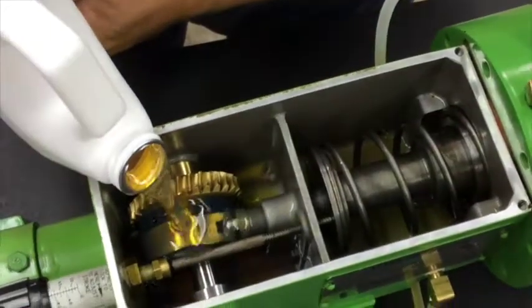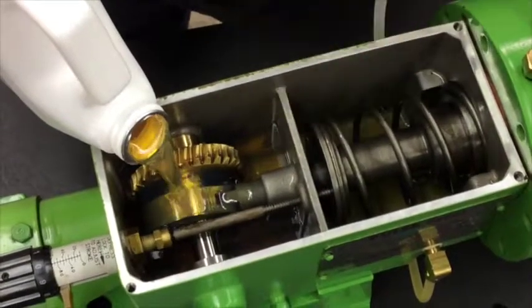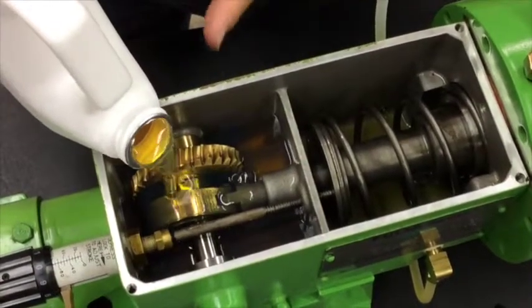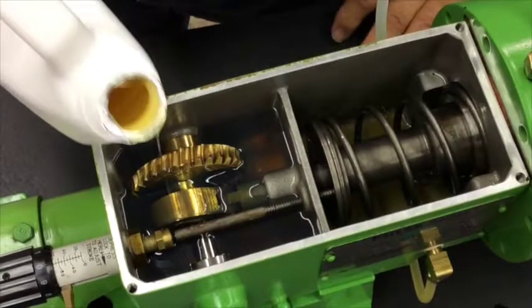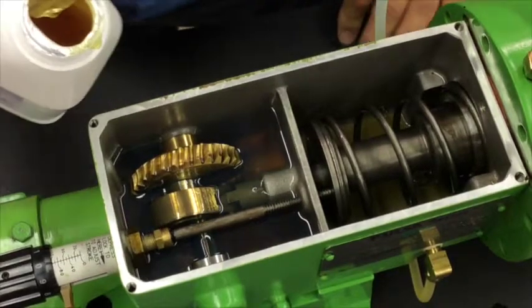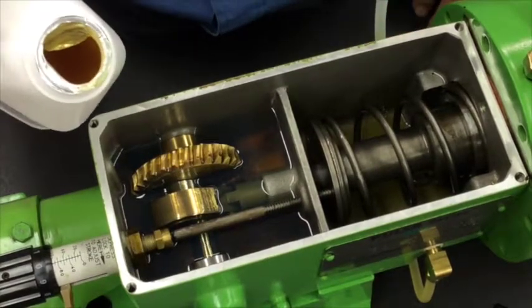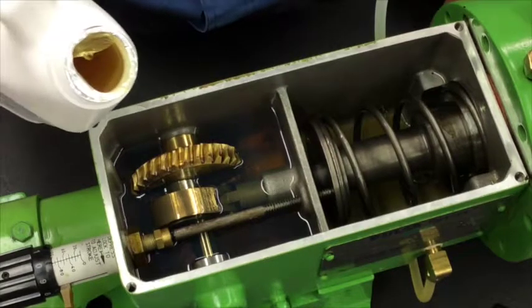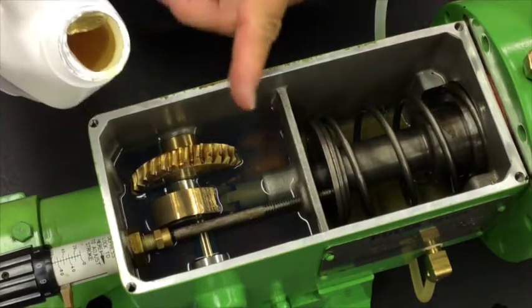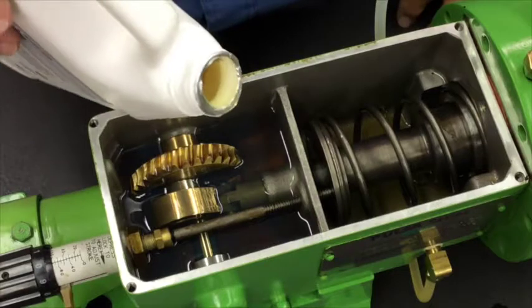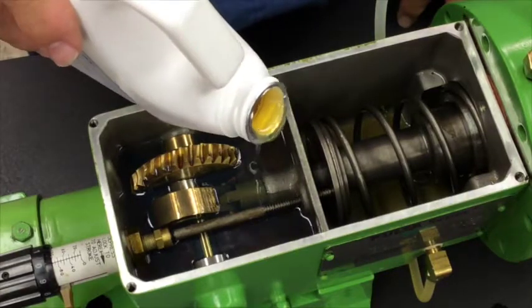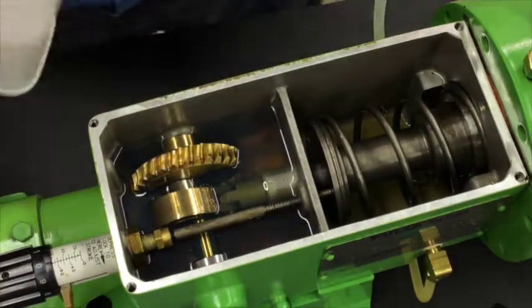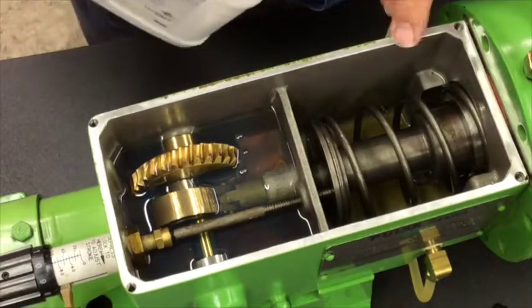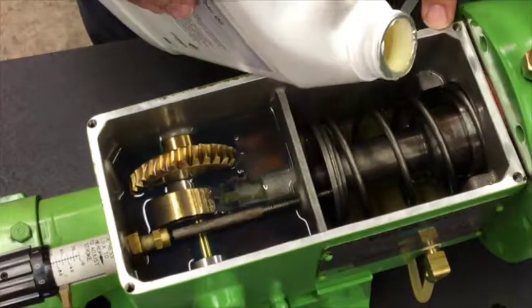Now please note that there's a divider here between the two chambers, so oil doesn't flow between the two chambers. And that looks pretty good. I've got it covering the crosshead right now. I'm going to add just a little bit more, that's good. All right, now the remaining oil I'm going to pour into the front portion of the pump body.